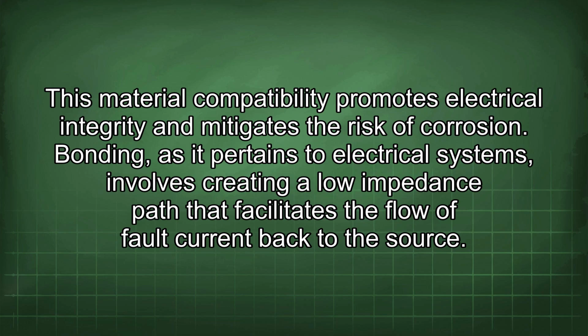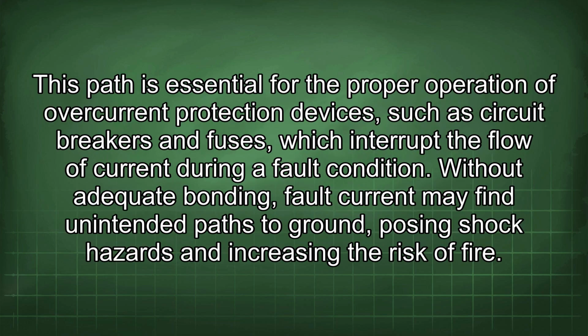Bonding, as it pertains to electrical systems, involves creating a low impedance path that facilitates the flow of fault current back to the source. This path is essential for the proper operation of overcurrent protection devices, such as circuit breakers and fuses, which interrupt the flow of current during a fault condition. Without adequate bonding, fault current may find unintended paths to ground, posing shock hazards and increasing the risk of fire.